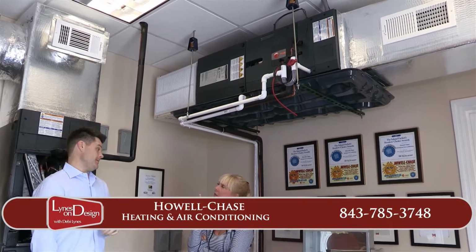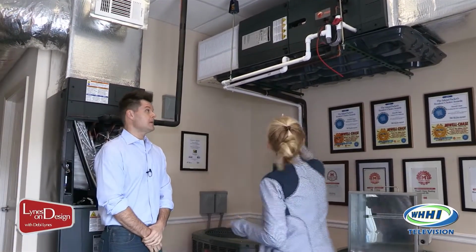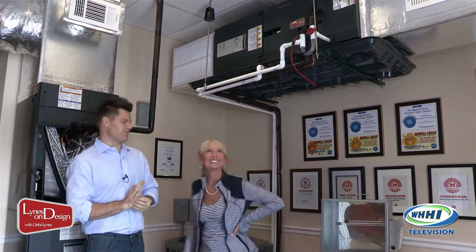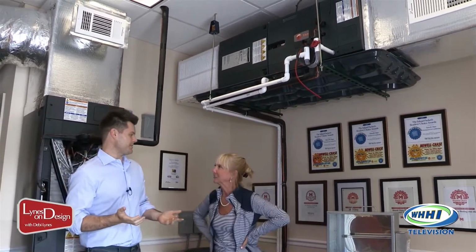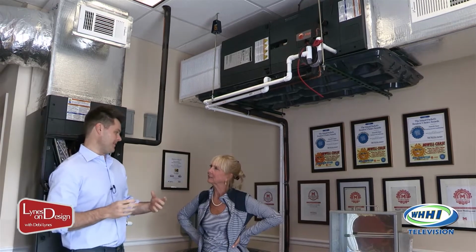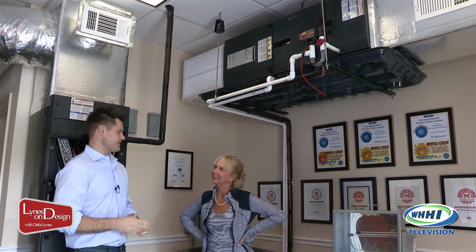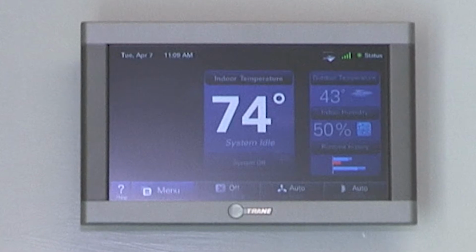So we are subtropic. How does that affect the quote unquote spring cleaning efficiency or effectiveness of our units? You have to imagine your HVAC system when it's 72 degrees outside. You're saying, oh, I'm not really running my system, it's not really doing anything. What it is actually doing is dehumidifying. It's nothing but a large dehumidifier at that point. It is pulling moisture from the air. You can walk into a home and have a temperature of 72 degrees, and it feels so uncomfortable. It's not a comfortable 72.